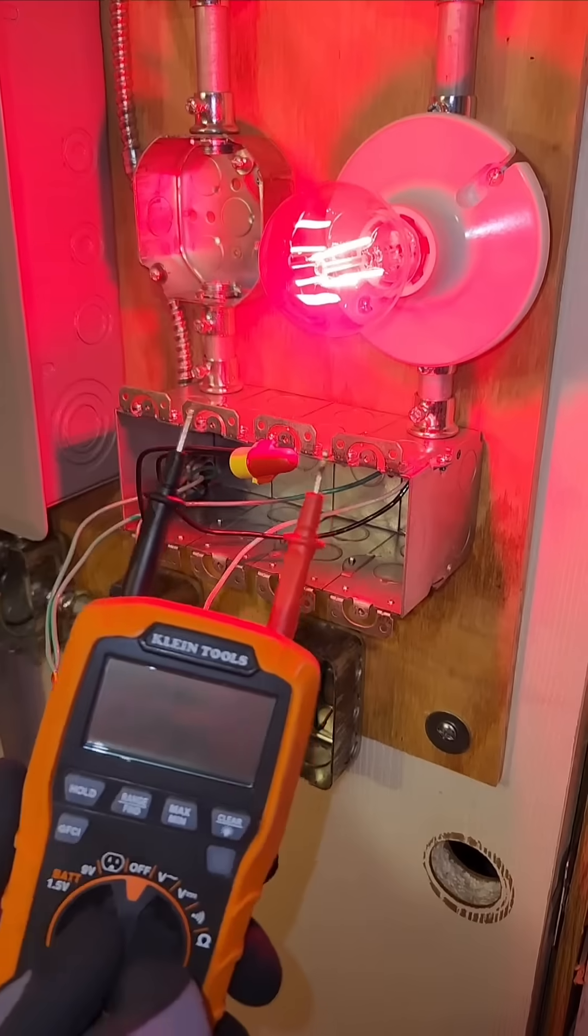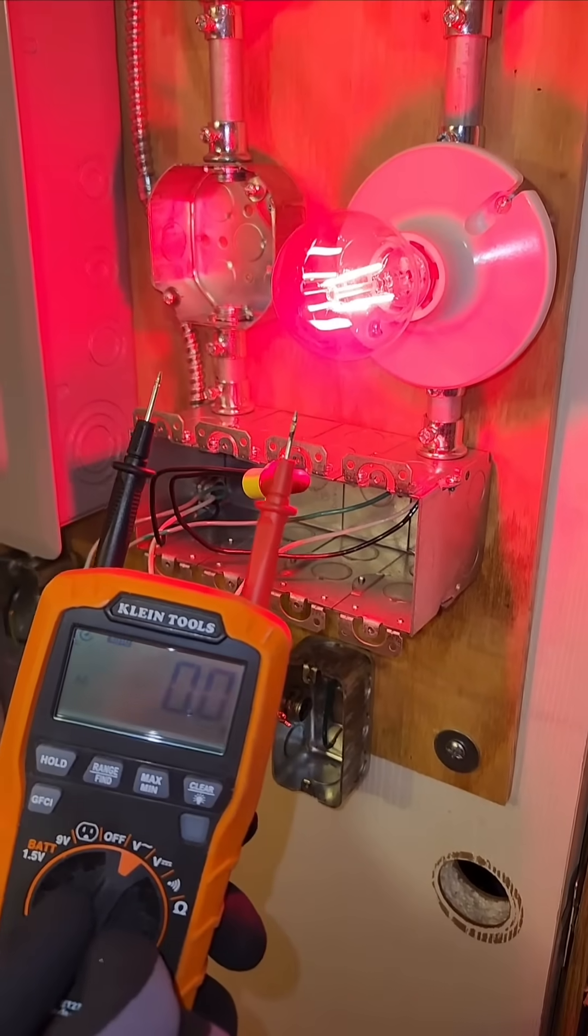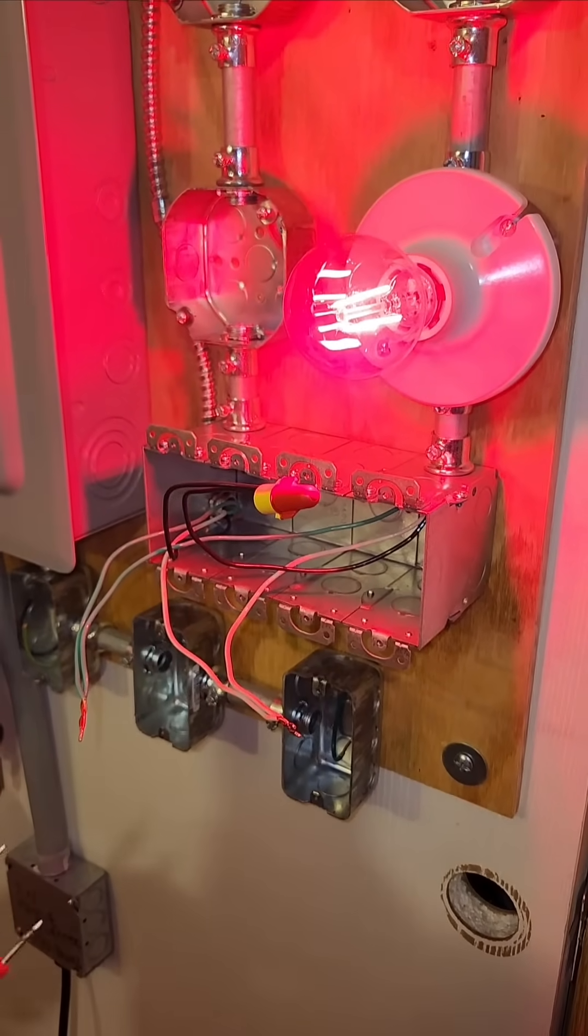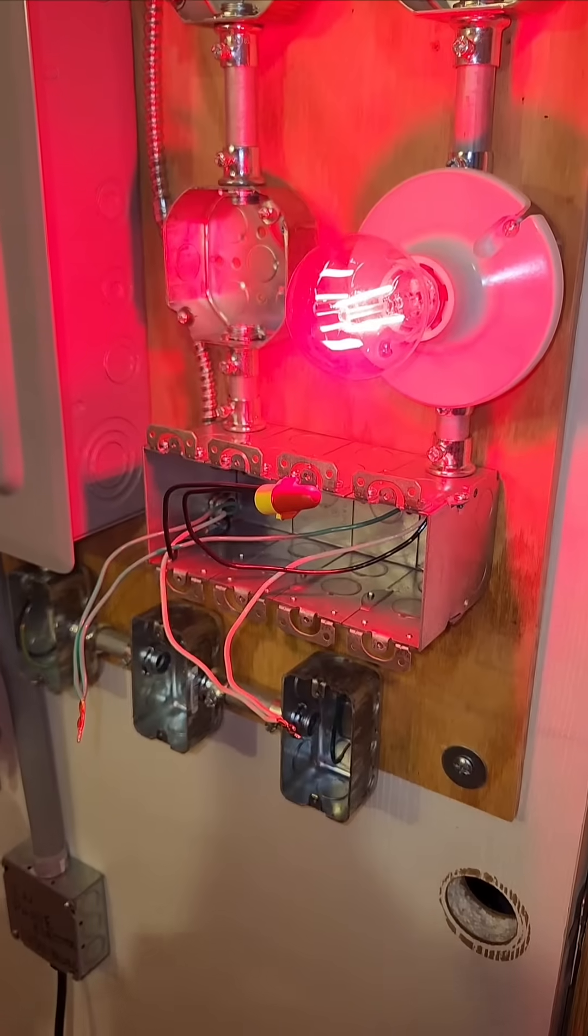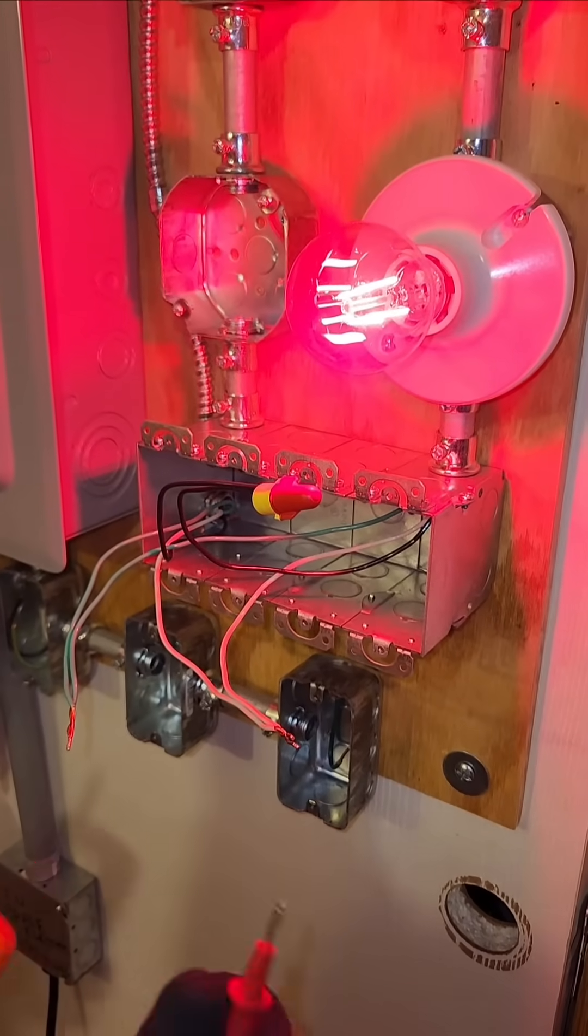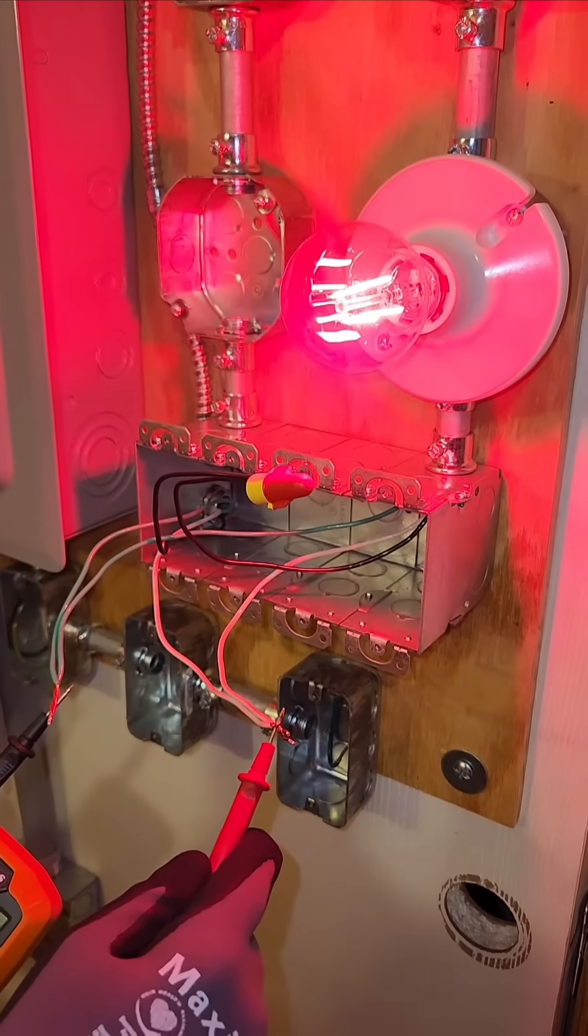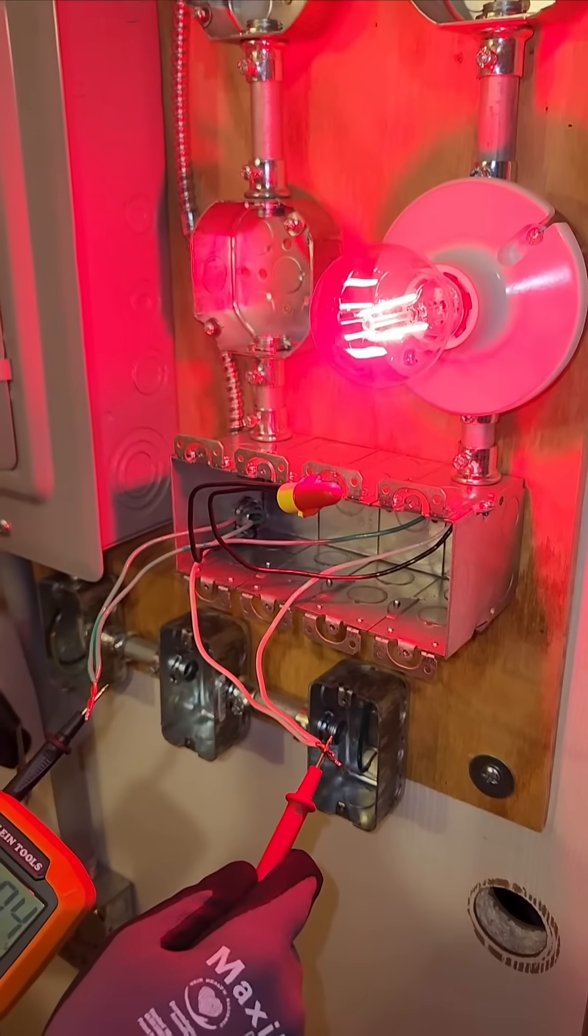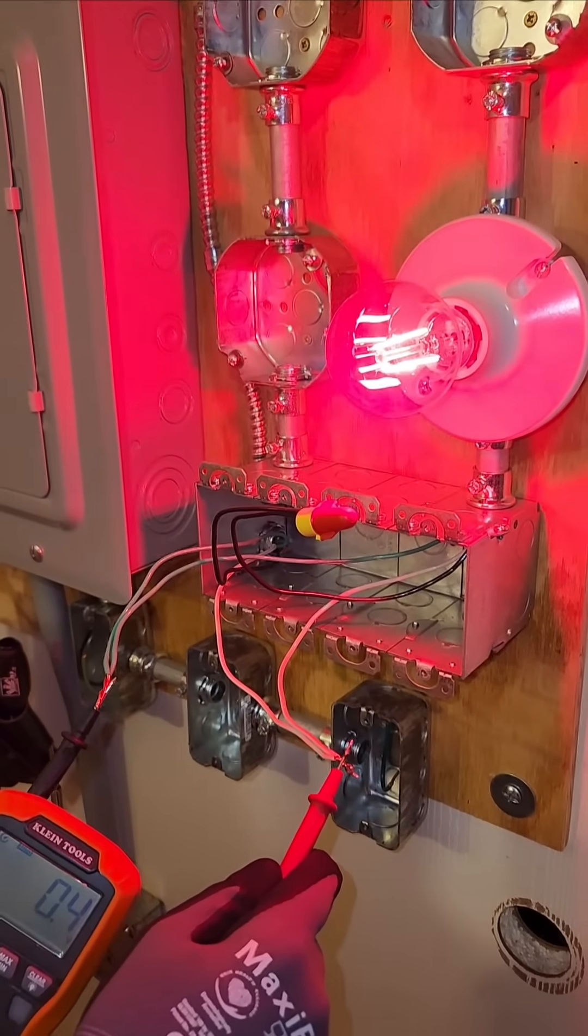Alright, so right now we have a fully functioning circuit that is properly grounded. So at this point in time we'll get zero volts approximately between the neutral and the ground.